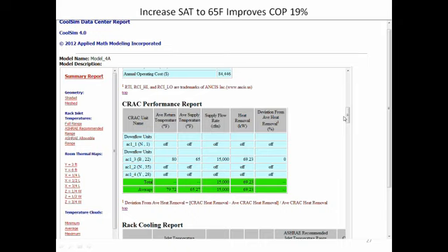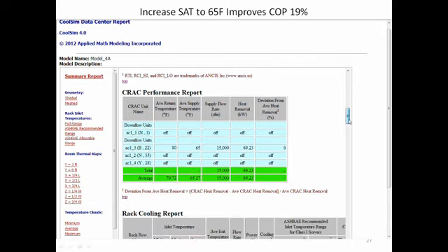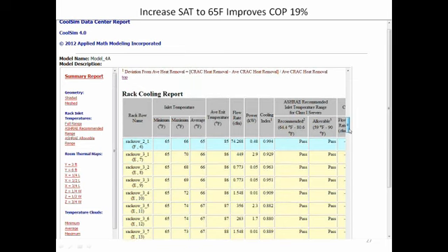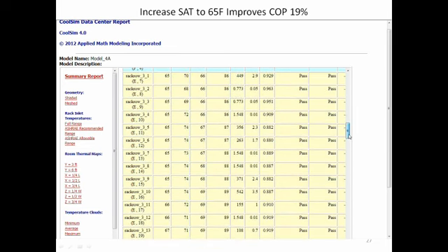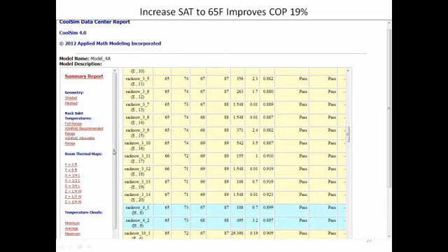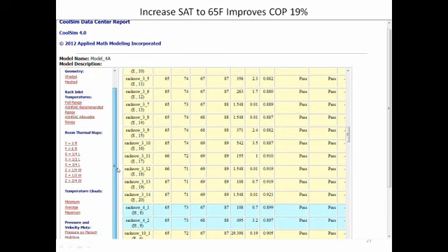Exactly correct. So what you would want to do here, right now I've got this particular CRAC unit turned on, AC1_3. I'd want to switch them, rotate them around, try this same model with each of the others turned on individually to make sure that it conforms to the specification. If so, you could set the CRAC unit up so that any one of the other three would come on, and you'd still have your N+1 case. So this one works pretty well. This is the optimal case.